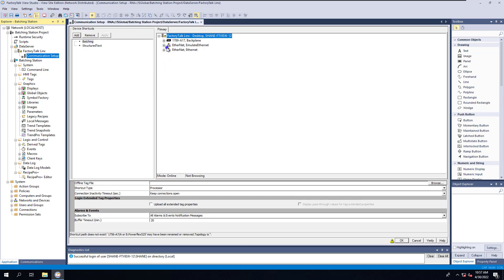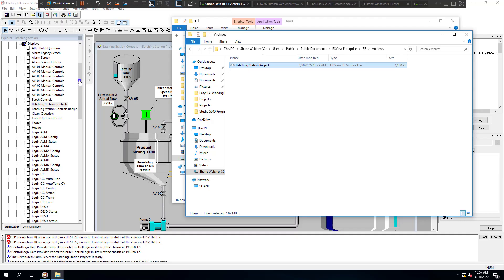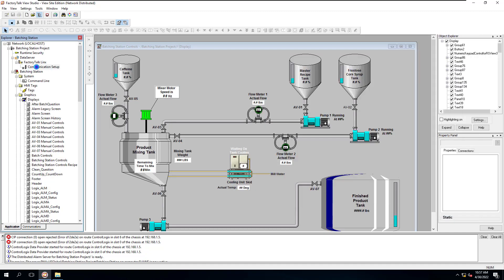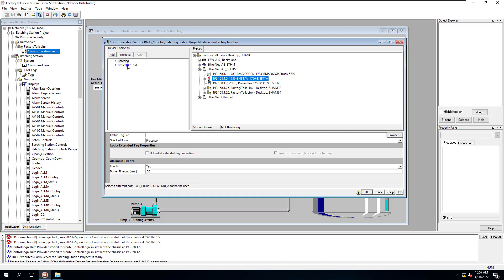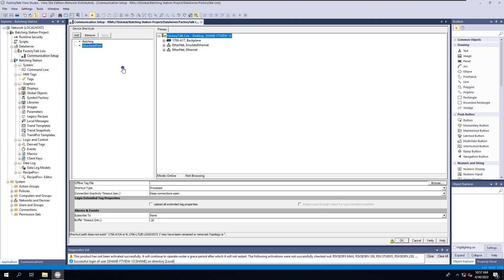Now I may have to come in here and repoint my shortcuts to where they used to be, just like we did on our old HMI backups, but that's not a big deal when it comes to everything you have to do to restore an HMI application. Just make sure you double-check and do due diligence to make sure you set the shortcuts again. All my shortcuts right here are not set. If you look at my other application, my HMI shortcuts have already been set - they know where they're going. Over here, they do not know where they're going, so we would have to make a connection and connect them.